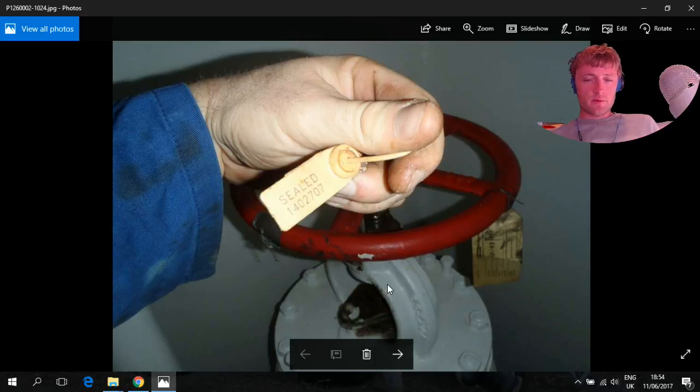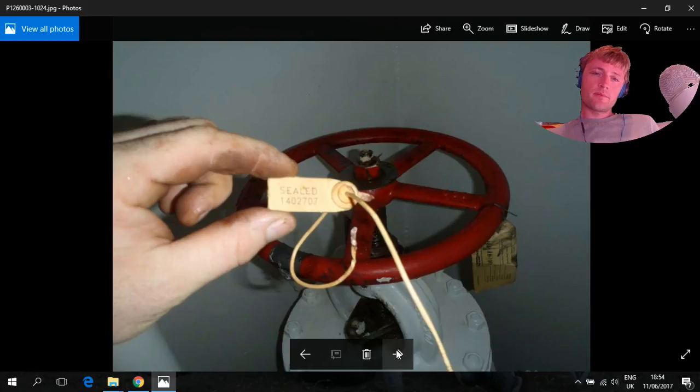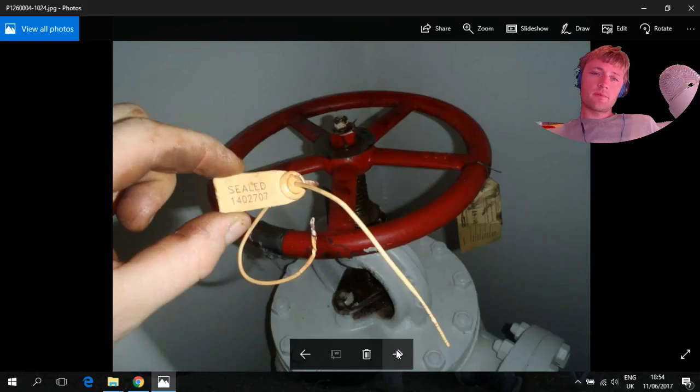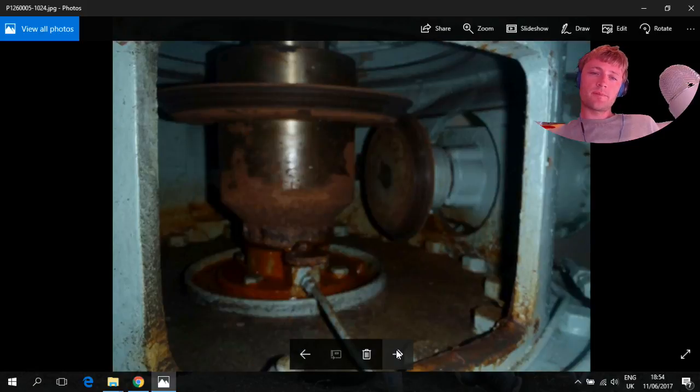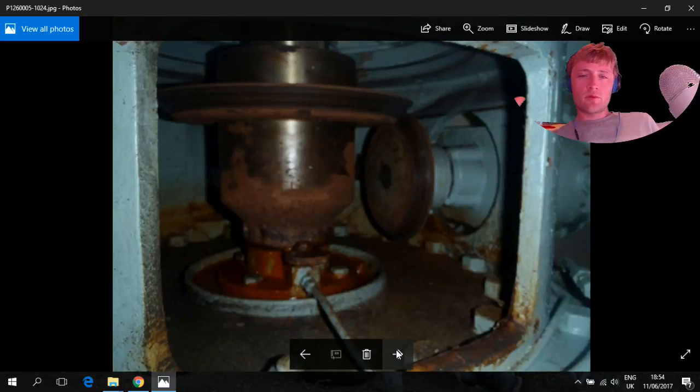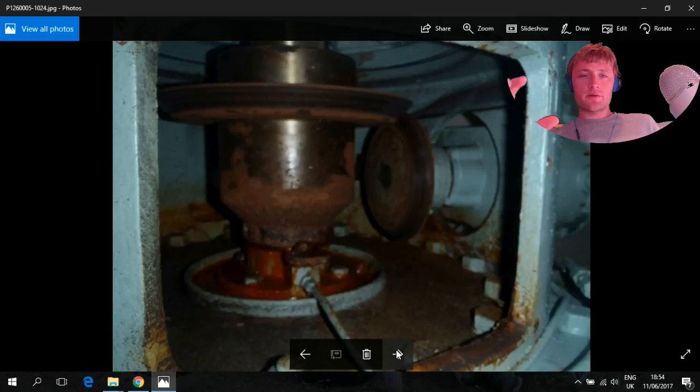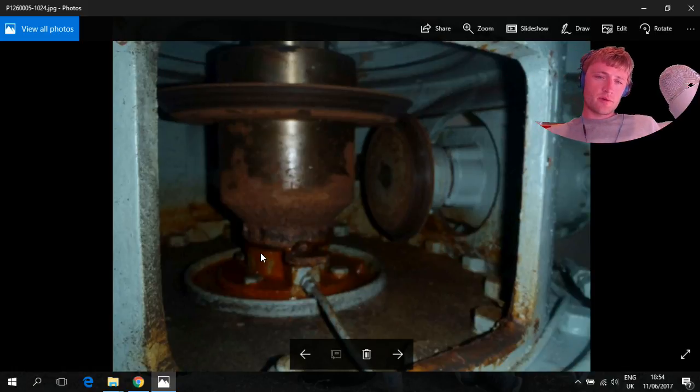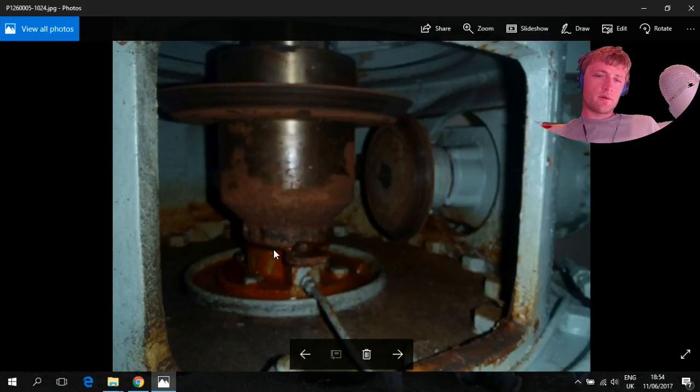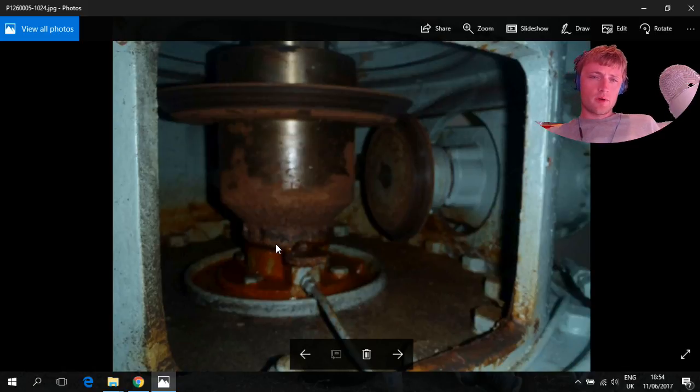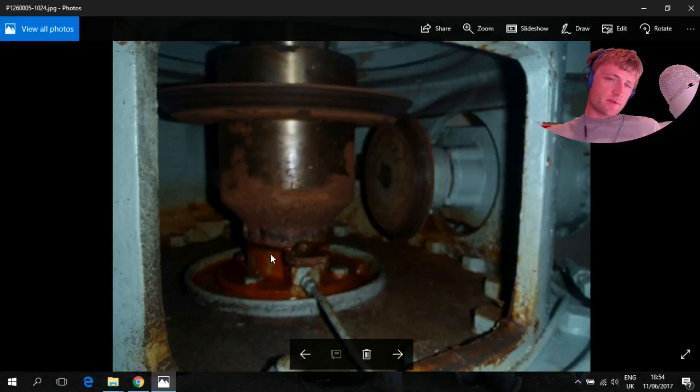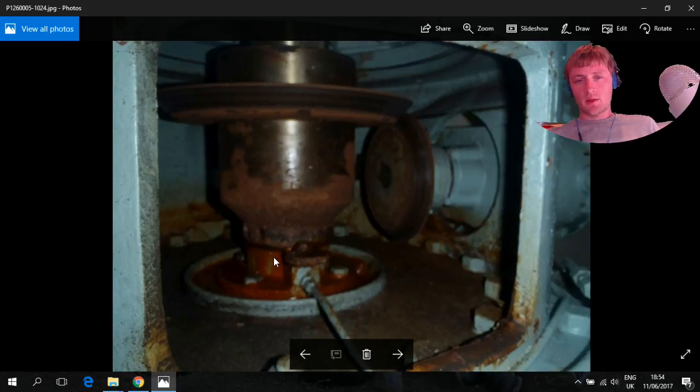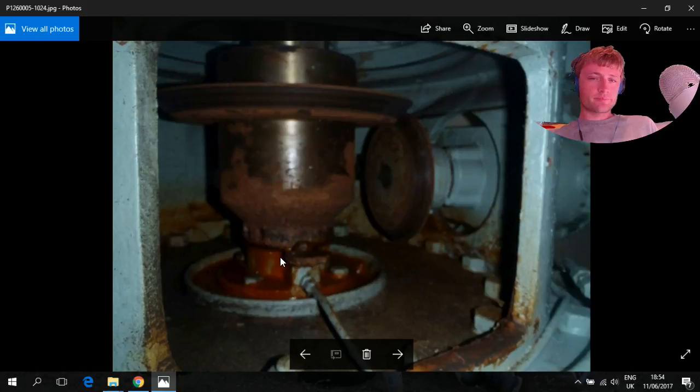We close the suction valve. The maintenance which we will make here is to clean the shaft. There was a leakage here in the seal but we didn't remove it. The leakage was small, but that was the main purpose—to determine the leakage.